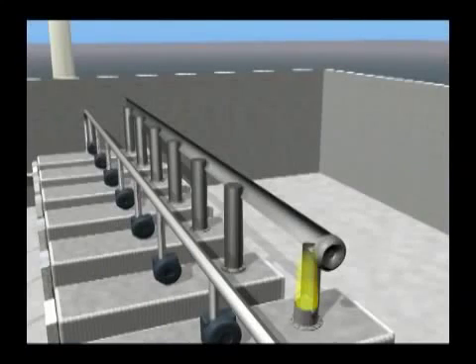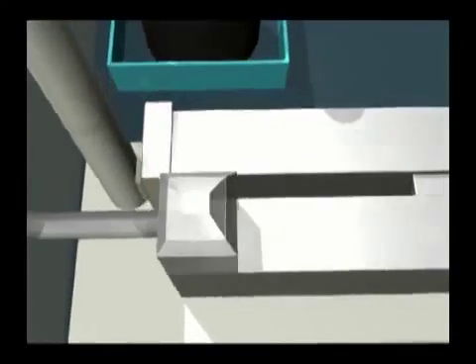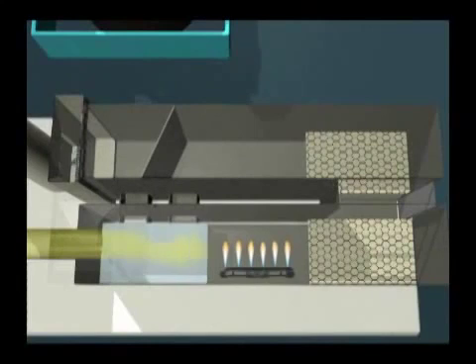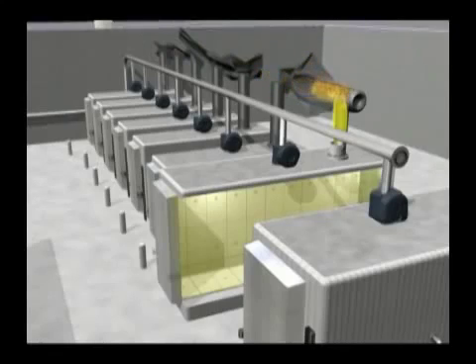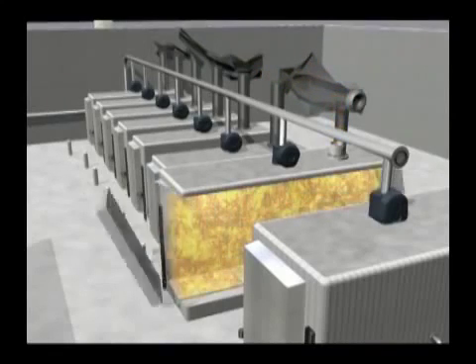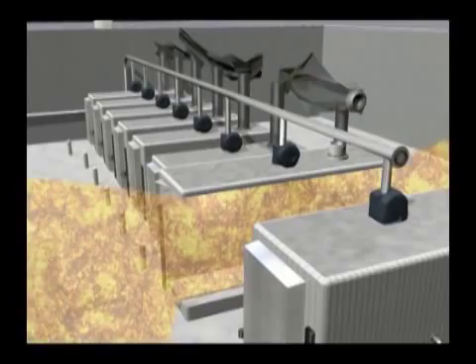This drew a large amount of ethylene oxide from the chamber through the back vent to the open flames in the oxidizer. The explosive gas ignited. A flame front traveled back through the ducting into the sterilization chamber, igniting the remaining ethylene oxide and causing a powerful explosion.